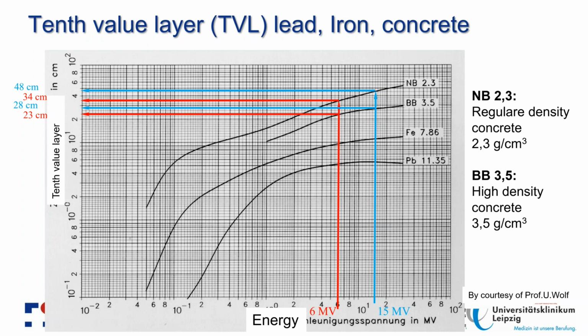So the discussion is, if you need more than one energy, what should be the second energy? We have historically 6 and 18 MV. 18 MV is way too much. With new technologies, new techniques like RapidArc or VMAT or IMRT, you could achieve very good conformality and very good homogeneity in the target, also with lower energy.